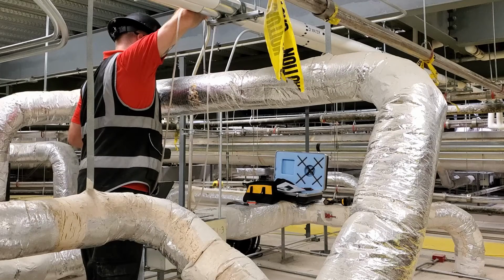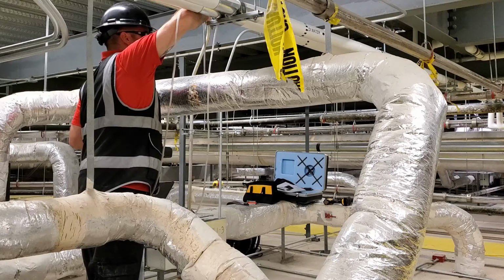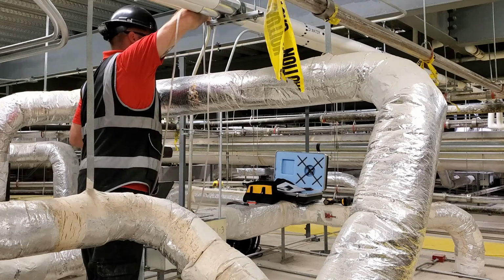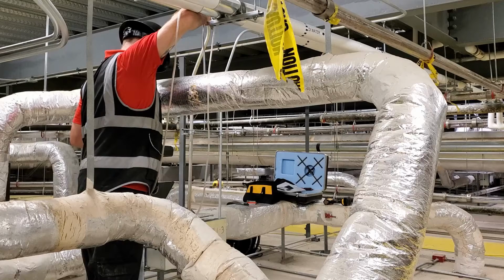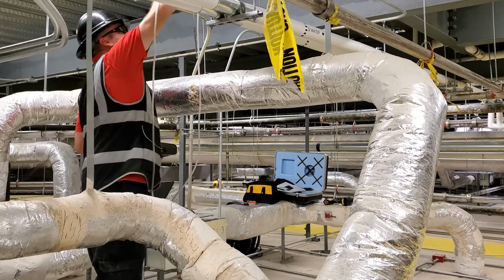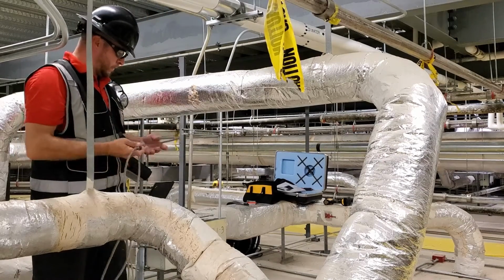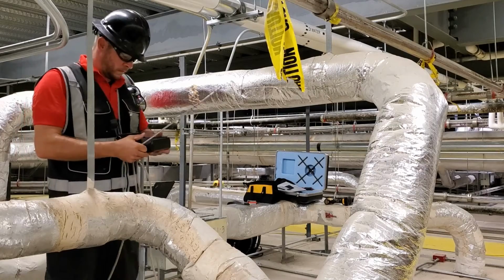So he's just going to finish up doing the vertical portion of the traverse, and then after he's done with that, he will take a static pressure. Now the reason to take a static pressure is, one, just lets you know what pressure the system was at, but also you can utilize it if you have to do another traverse just to check to make sure that the calibration held. You can utilize the static to see if you're getting close prior to doing that traverse.